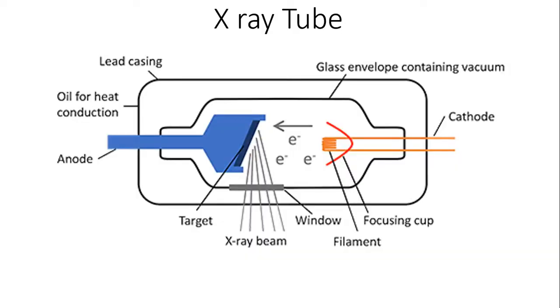The main part of an X-ray device is the X-ray tube, also called the X-ray generator. The X-ray tube consists of a glass envelope embedded in a lead casing. Inside this evacuated glass tube, there are two main parts: the anode, which is held at a positive potential, and the cathode, held at a negative potential — a DC voltage is applied between them. The cathode is fitted with a filament.